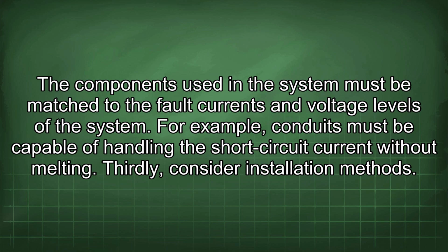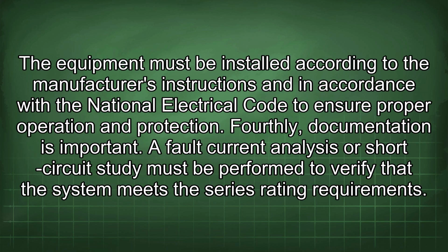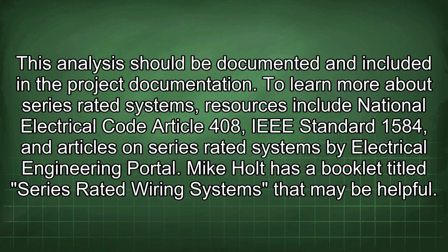Thirdly, consider installation methods. The equipment must be installed according to the manufacturer's instructions and in accordance with the National Electrical Code to ensure proper operation and protection. Fourthly, documentation is important. A fault current analysis or short circuit study must be performed to verify that the system meets the series rating requirements. This analysis should be documented and included in the project documentation.